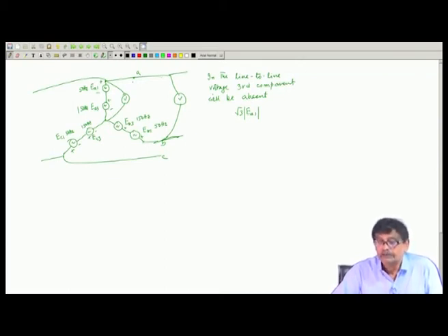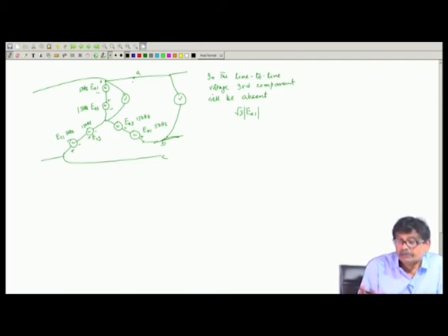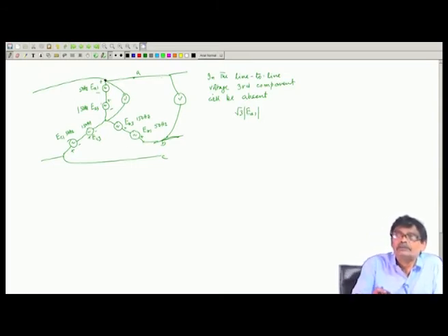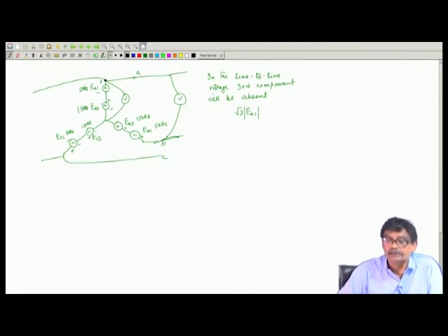because third harmonic flux voltages will be cancelling out in the lines, because they are cophasal. Then to avoid this, and therefore, this terminal, this voltage what I was telling, instantaneous value may be 30% higher than the fundamental component of this voltage. That is how the stressing upon the insulation comes in. We cannot allow this to happen in general.